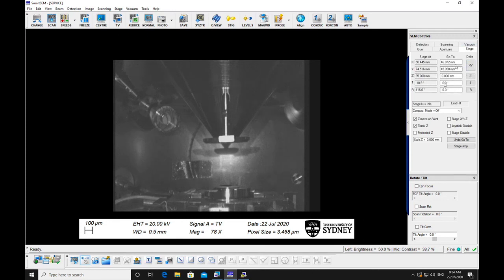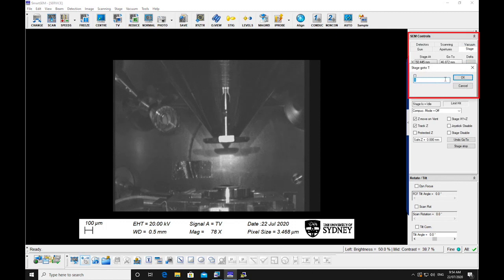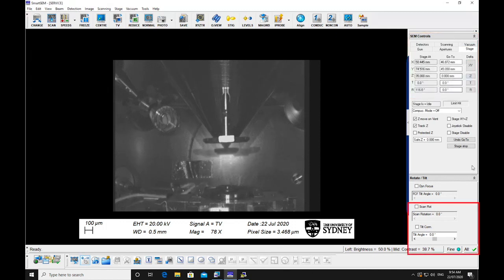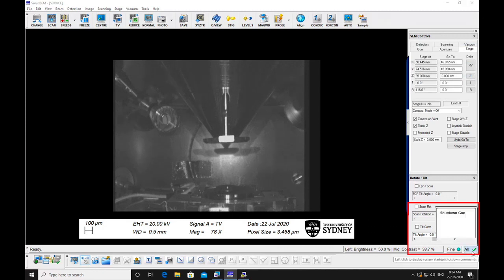Return stage to tilt 0 degrees via the stage tab on the SEM control window. Check to see if the beam is on, represented by a green tick next to all. If so, click on it and select shutdown gun.